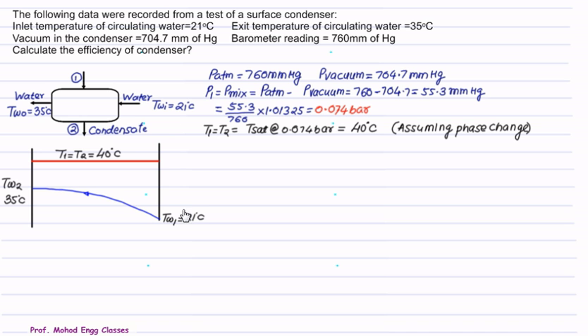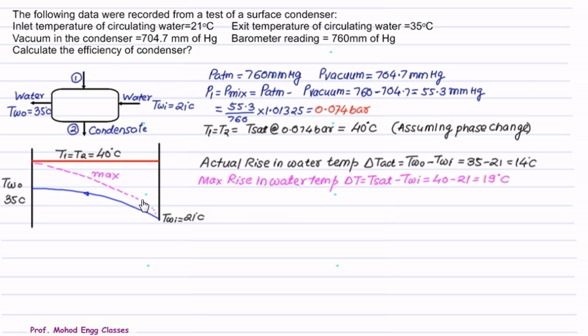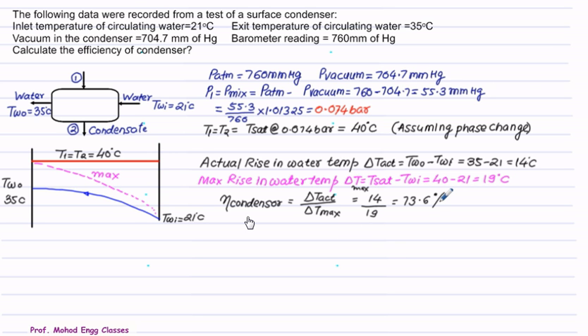Water enters at 21°C and leaves at 35°C. The actual rise in water temperature is ΔT_actual = TWO − TWI = 35 − 21 = 14°C. The maximum possible rise is ΔT_max = T_sat − TWI = 40 − 21 = 19°C. Condenser efficiency is defined as actual rise divided by maximum possible rise: 14/19 = 73.6 percent.